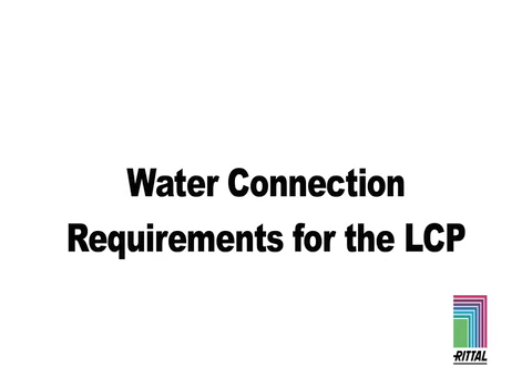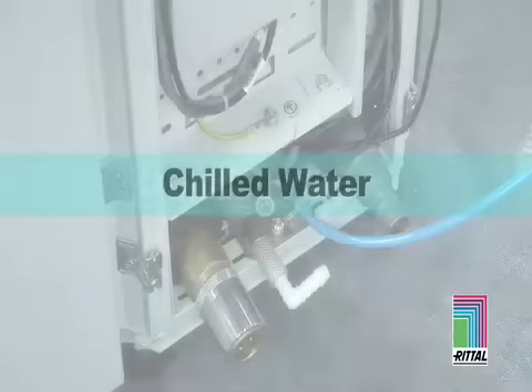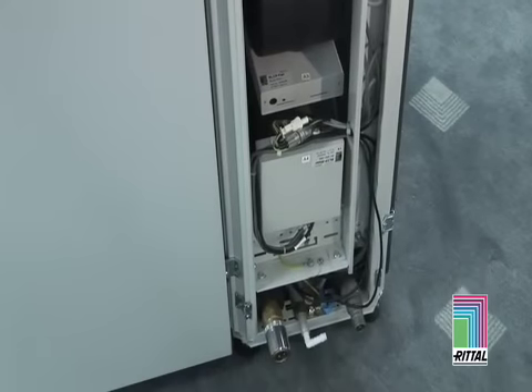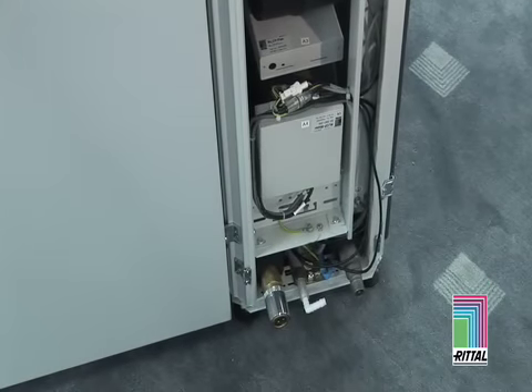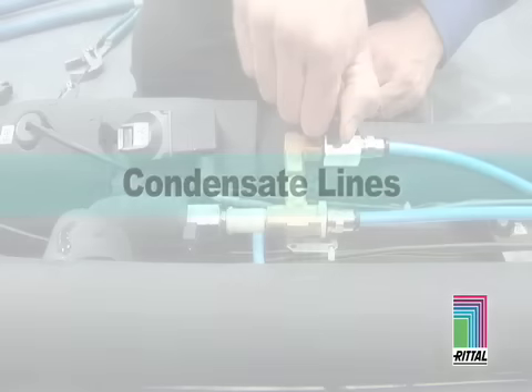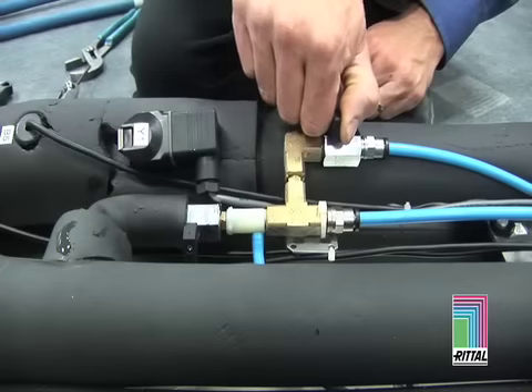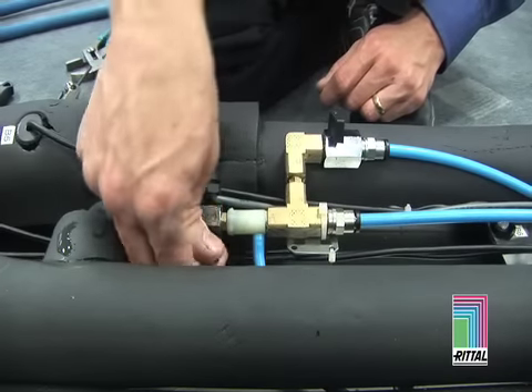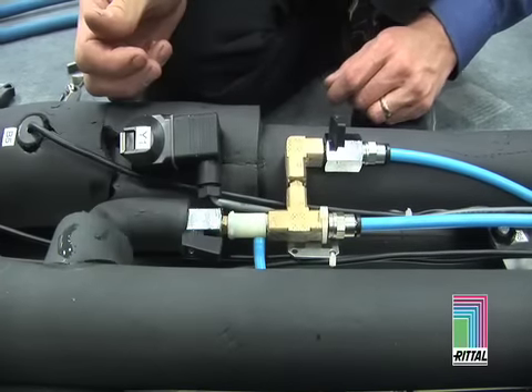Water connection requirements for the LCP. Chilled water: chilled water from a central chilled water plant is fed into each unit through the bottom or rear chilled water connections. Condensate lines: condensate from the unit is pumped out of the system through the drain lines, or can be configured to pump back into the chilled water return lines if required.